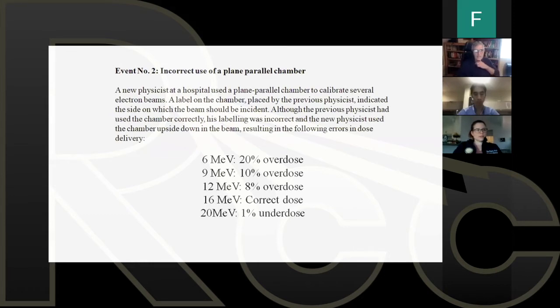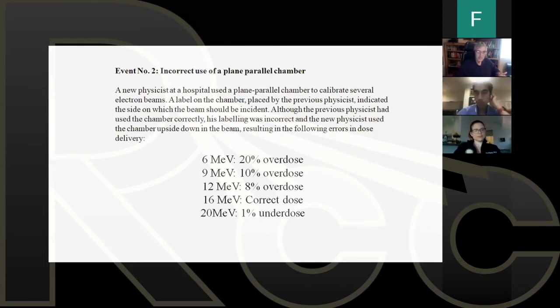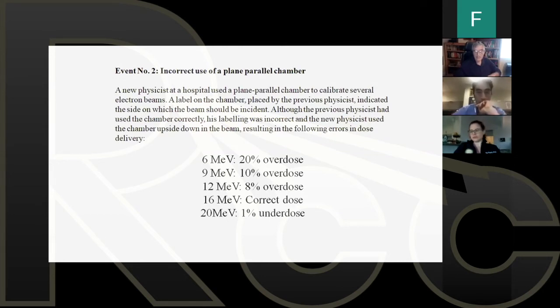The physicist had used the chamber correctly. The labeling was incorrect and it was never changed. The new physicist came in, saw the label, which was incorrect, assumed it to be correct. And as you can see, the following errors in dose were recorded until the error was caught. This is a mechanical error in a transition from one physicist to another. And something as simple as an incorrect label could cause severe overdose and even some underdose.